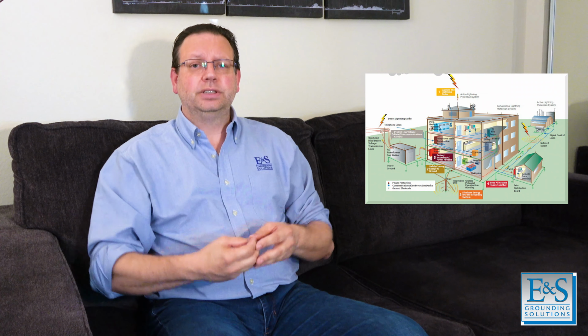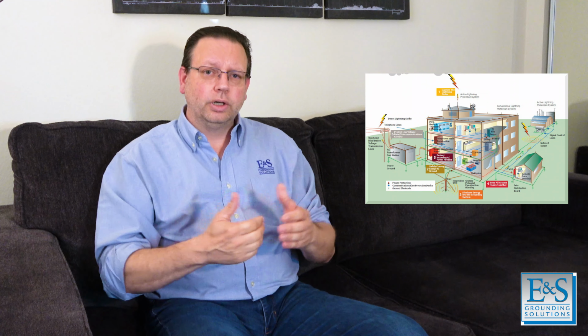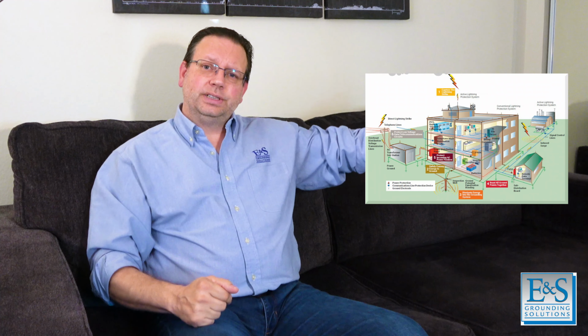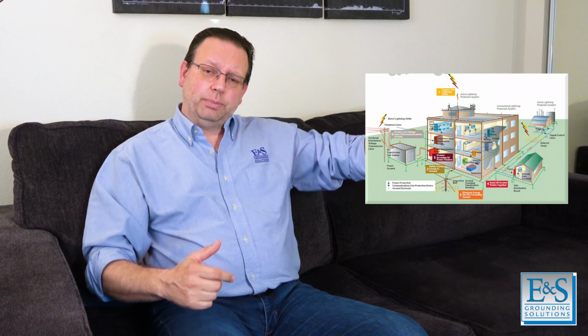Frankly, a good lightning protection system always includes a ground loop. Putting individual ground rods is never a complete grounding system, and our code should really honestly reflect that. They currently don't, but they should. So that ground loop not only protects us from the incoming wave, but it helps to make sure that we stay at even potential at all times.